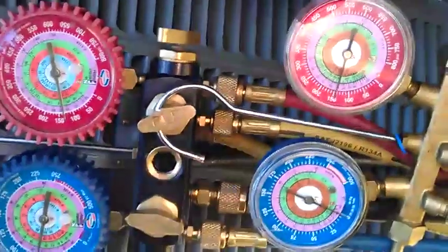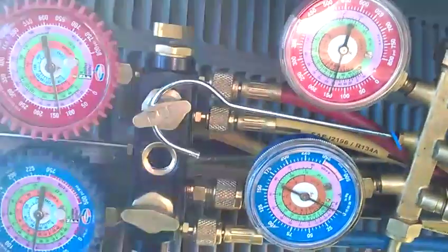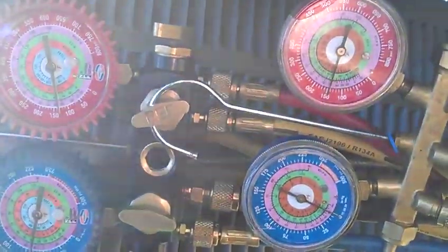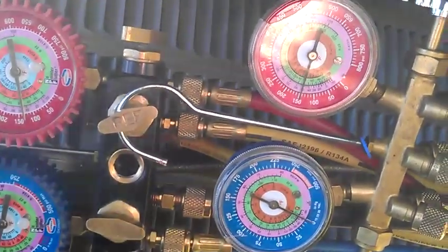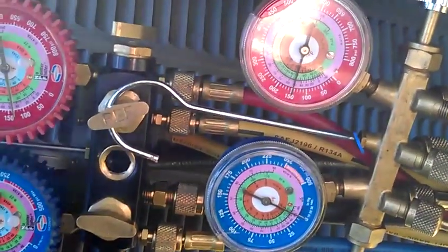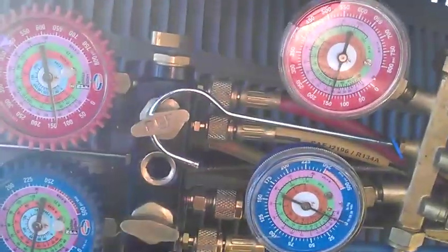Like I said, I think it's going to be real valuable to just get one high pressure gauge because when you are in heat mode both lines can blow your low pressure gauge. Just get one gauge, hook it straight up to a hose and have a spare gauge hanging here so you can do these tests.